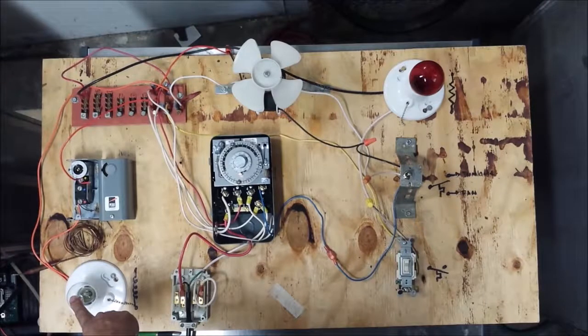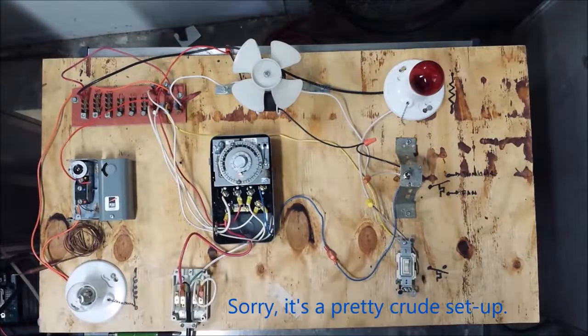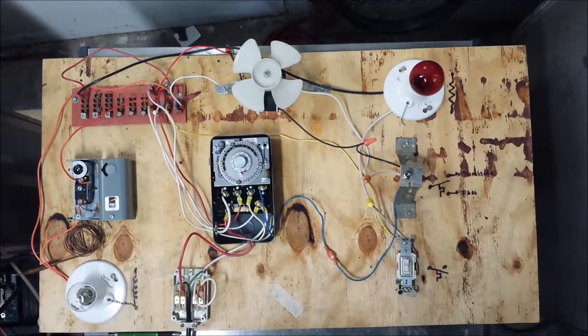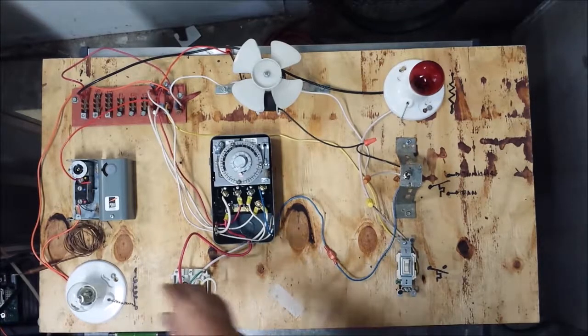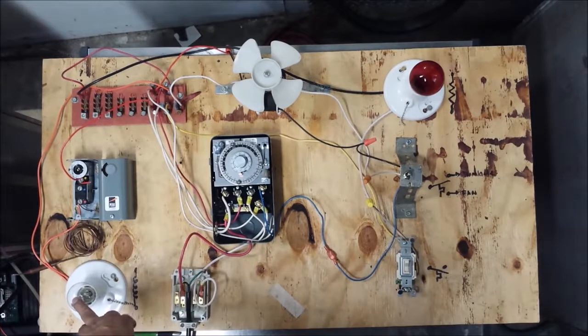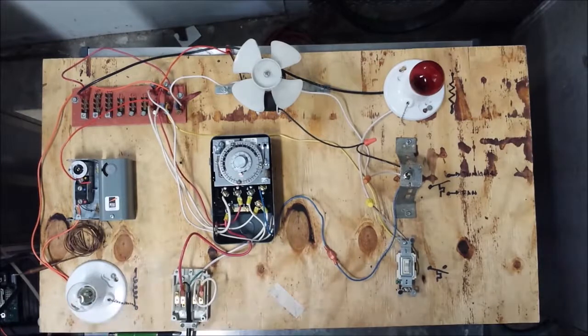And the valve itself is not in here, but if the valve opens up, it allows refrigerant to flow through the system. If the valve is closed, it stops refrigerant flow. The way that happens is if this coil is either energized or de-energized. So if the light is on, that means the coil is energized and the valve is open, allowing refrigerant to flow. If it's not on, refrigerant flow stops.